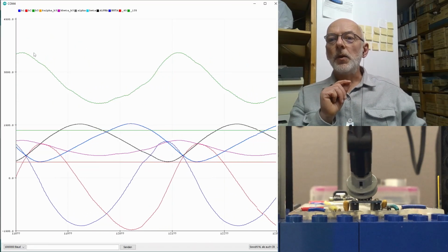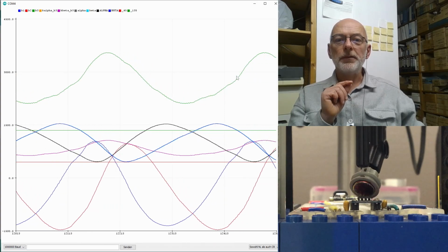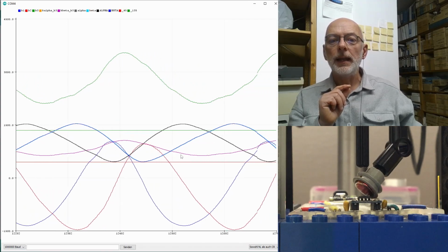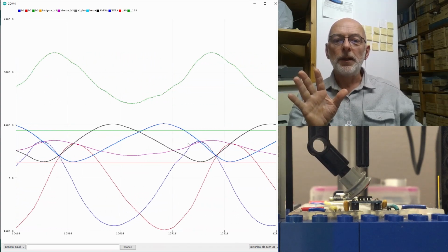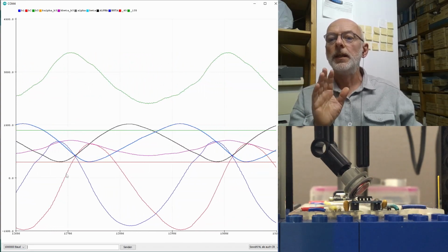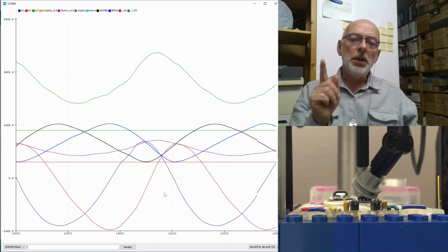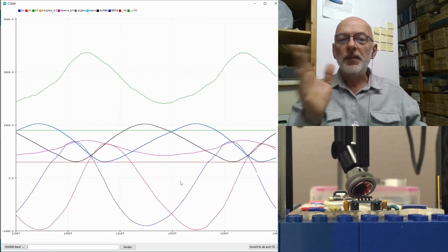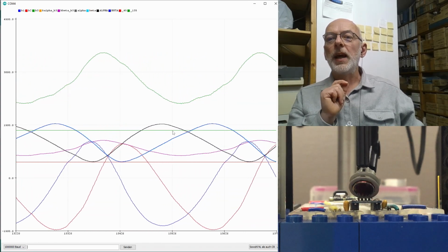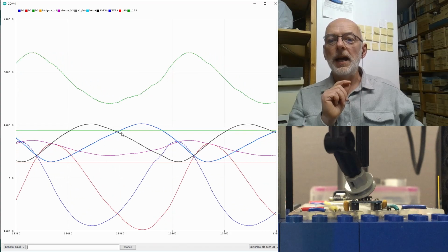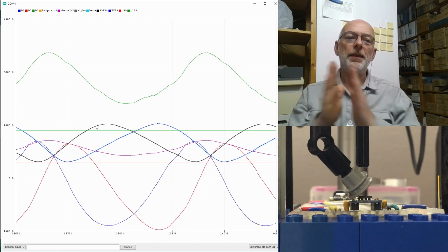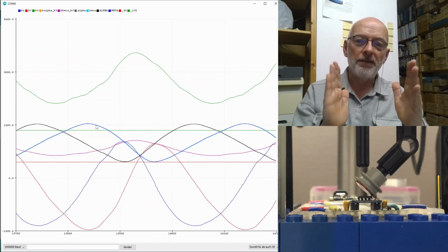And look at that. So here is our raw B3 respectively set signal, and that is now scaled down again in lilac at the same level, maximum level, aboutish as our blue B1X signal and reddish B2Y signal. And suddenly our angle measurements here make a lot more sense. So we have still black the alpha angle and blue the beta angle, and they are nicely 90 degrees phase shifted.